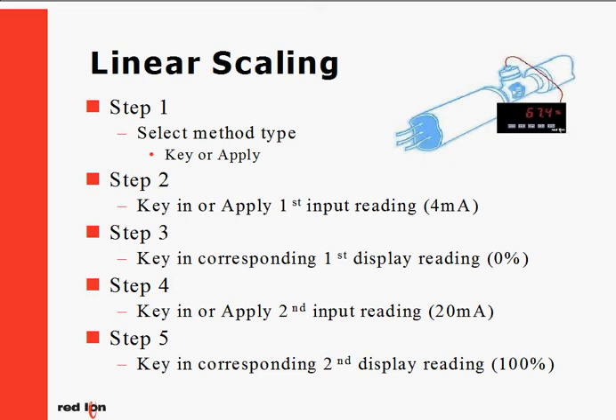The first step is to select the proper scaling method: Keyin or Applied. The next step is to Keyin or apply the low input signal. In our example, that would be 4 milliamps. Next, in step 3, we keyin our corresponding display reading for the low point, or in our example, 0 percent. Now the first half of the scaling is complete — the low point, or minimum.